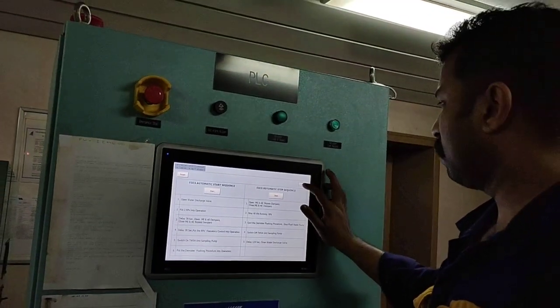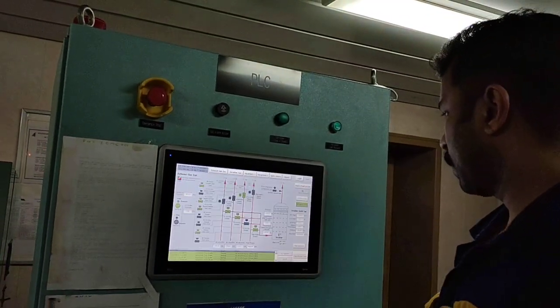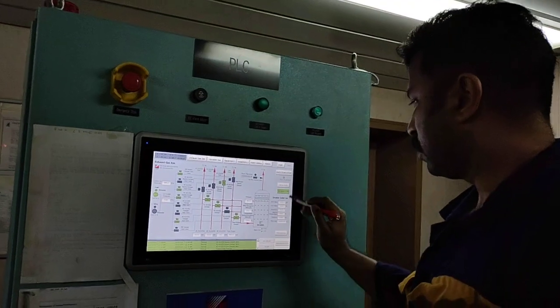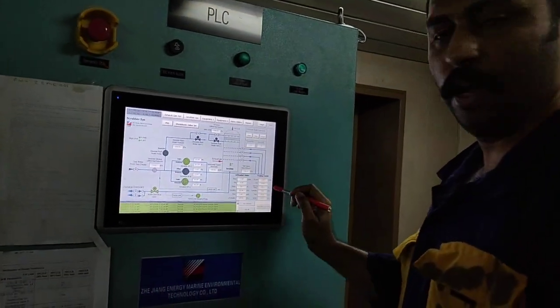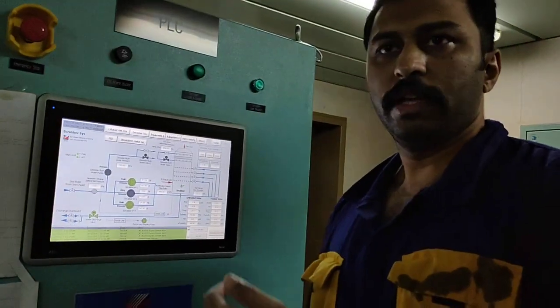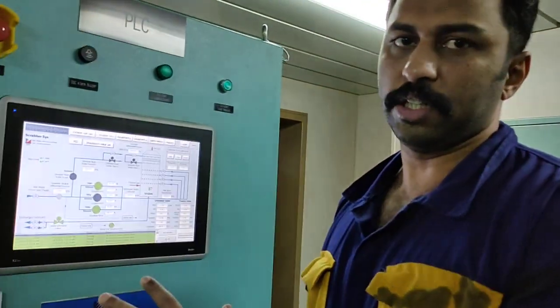you will usually get an alarm like flow, there is no flow, treated water, no flow alarm. There is no flow because the pump either not taking suction or the filter is dirty.